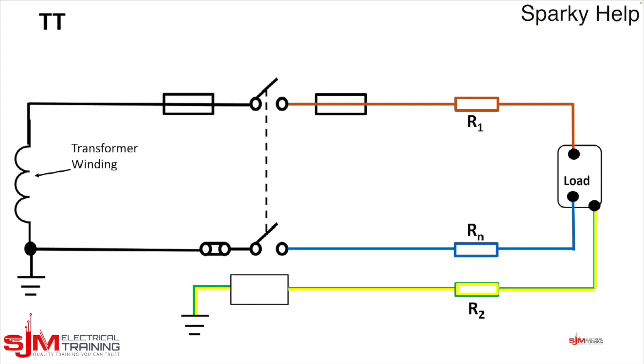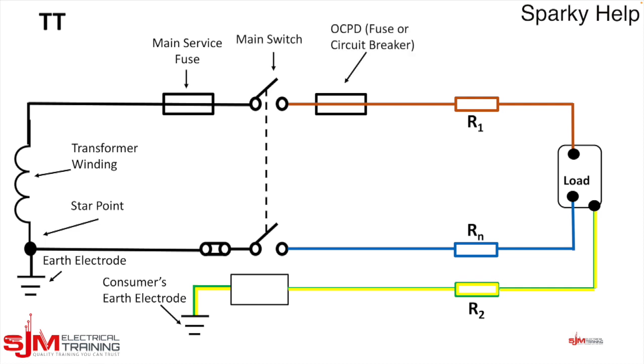Let's go round then. We have the transformer winding, we have the star point within the transformer, we have the consumer's earth electrode, which is put in by ourselves if we're electricians, we have the earth electrode on the transformer itself, we have the main service fuse, we have the main switch in this case double pole, we have the overcurrent protective device fuse or circuit breaker, the exposed conductive part.